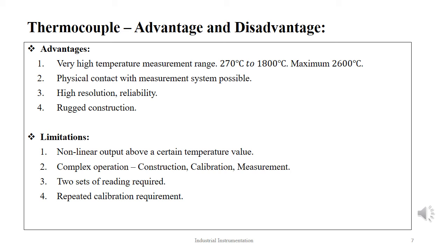The limitations of the thermocouple are, however, after a certain temperature value, the scale tends to become nonlinear. The thermocouple operation, from construction to calibration to measurement, is somewhat complex. It requires 2 sets of measurement for full comprehension. The device requires calibration sometimes even in the middle of the usage.